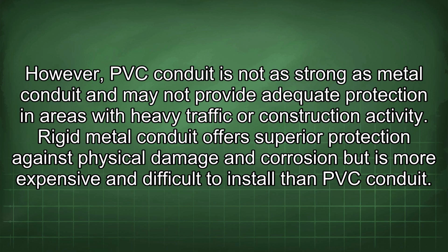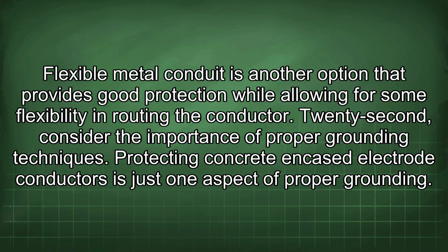traffic or construction activity. Rigid metal conduit offers superior protection against physical damage and corrosion, but is more expensive and difficult to install than PVC conduit. Flexible metal conduit is another option that provides good protection while allowing for some flexibility in routing the conductor.